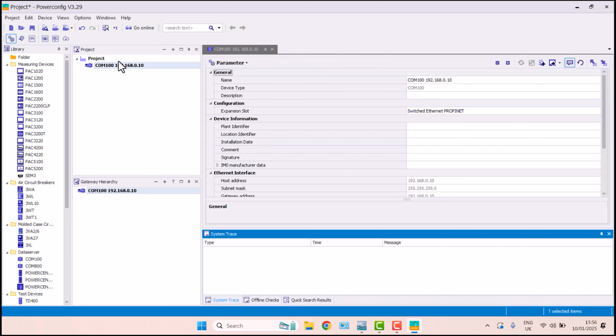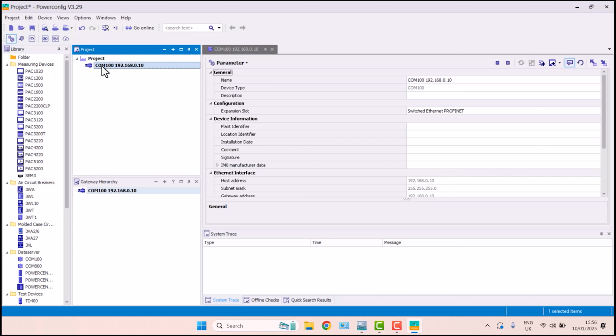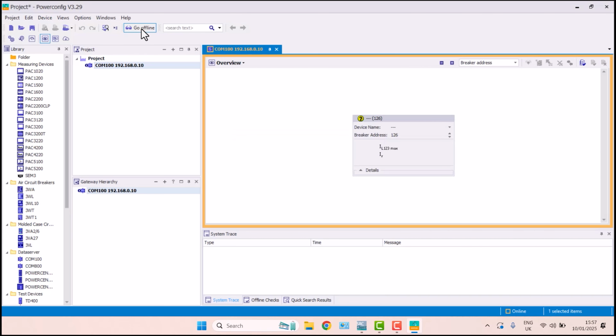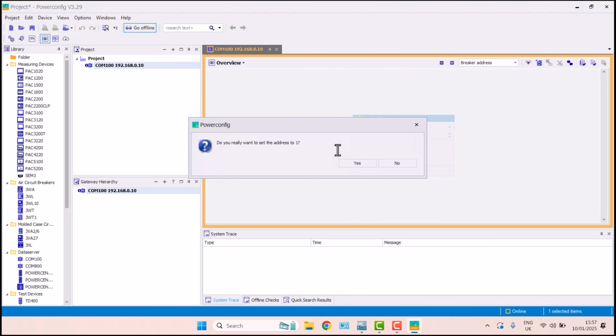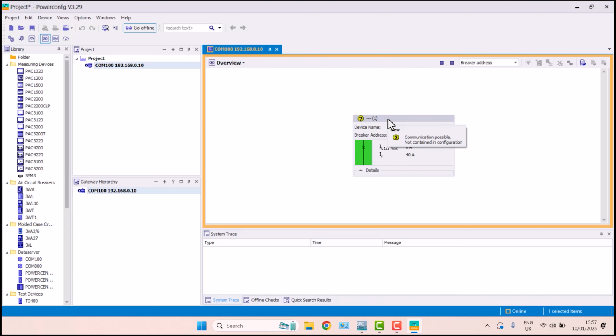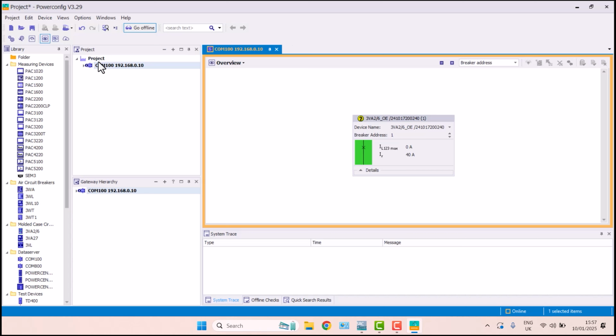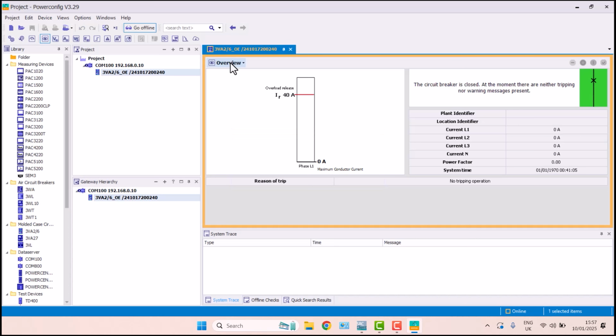And you'll notice over here that we've got our COM100. This COM100 is currently connected to a single 3VA2, so we need to search for that now. If we go into Overview and then go online, it'll find anything that is physically connected to it. So straight away here, it has found a single breaker. I'm going to readdress this breaker as 1. And I'm then going to add it into the project, so I just click on the top tab and then create selected breaker. What that has done now is it's added it to our project under the COM100. If we go into this, we can then see the live state of it. To prove that, I can switch this off and it will show that it's disconnected.